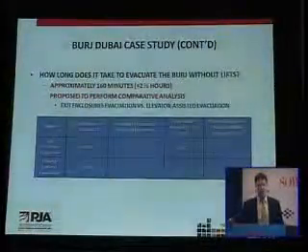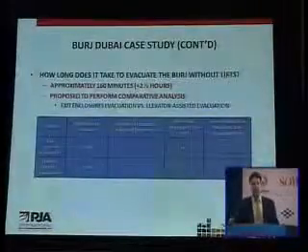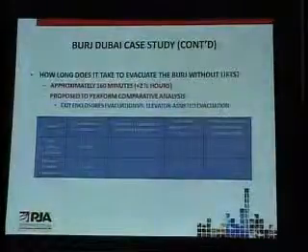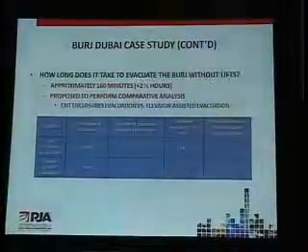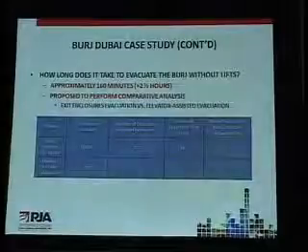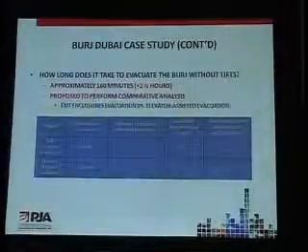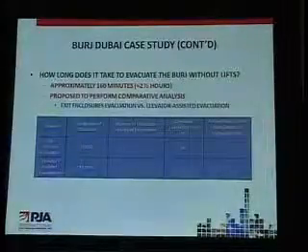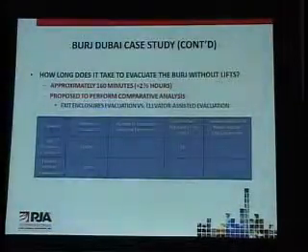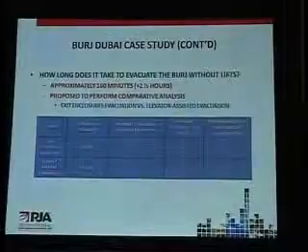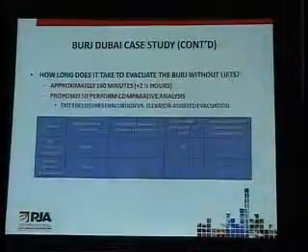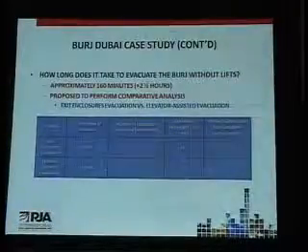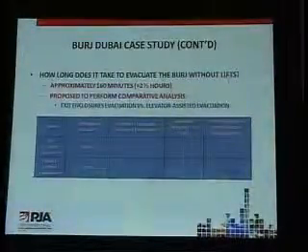So just to put it in perspective, how long would it take to evacuate the BURJ without any lifts? Well, we did a comparative analysis with EMAR to determine how many lifts they would like to upgrade to be used. We did our base calculation and found that it's going to take about 2.5 hours to evacuate the BURJ. And that's an ideal situation, assuming that people are actually physically fit to evacuate. And we knew that that wasn't going to be a solution, so we had to come up with something else.